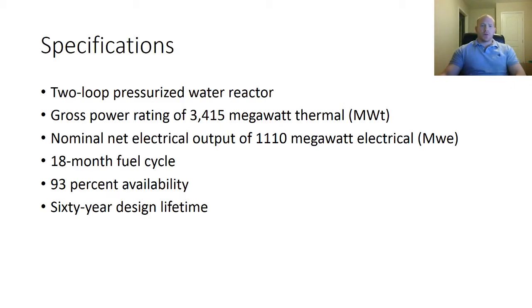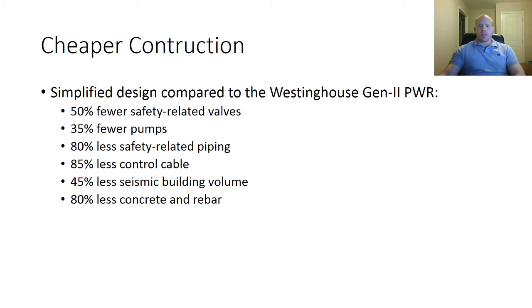All right, so the AP1000, it is a 2-loop pressurized water reactor, has a gross power rating of 3,415 megawatts thermal, 1,110 megawatts electrical. It has an 18-month fuel cycle, 93% availability, 60-year design lifetime. The AP1000 is simplified design and cheaper to construct compared to its cousin, the Westinghouse Gen 2 pressurized water reactor. It has 50% fewer safety-related valves, 35% fewer pumps, 80% less safety-related piping, 85% less control cable, and 45% less seismic building volume, and 80% less concrete and rebar.